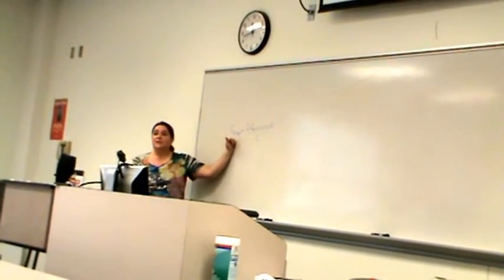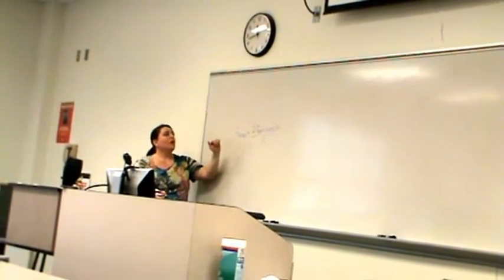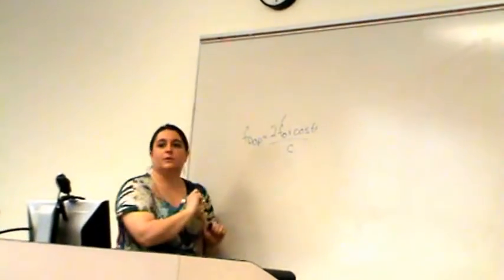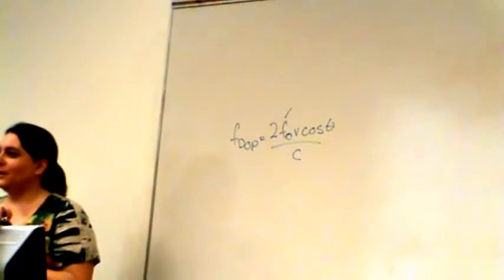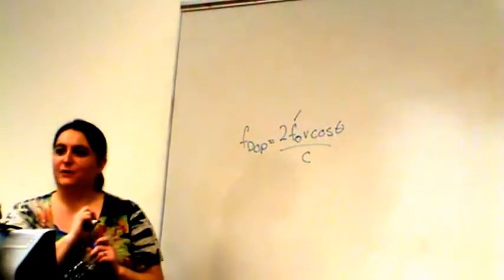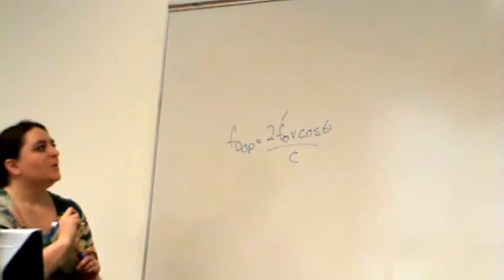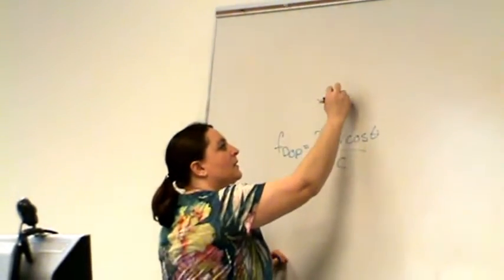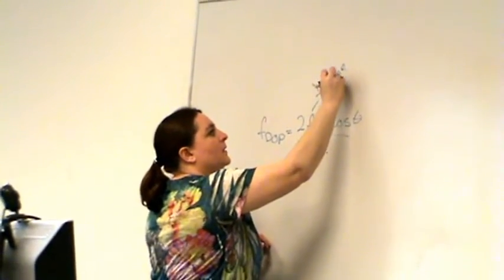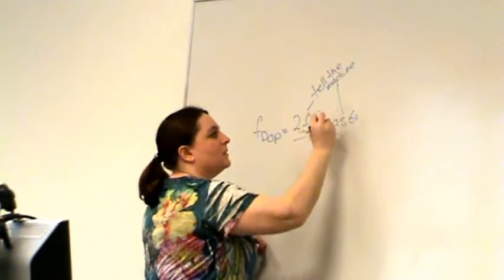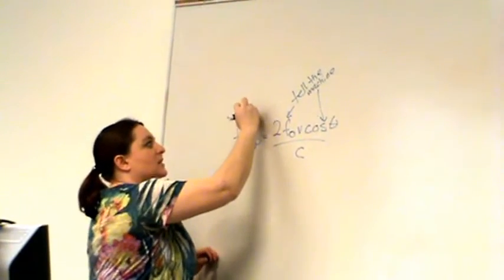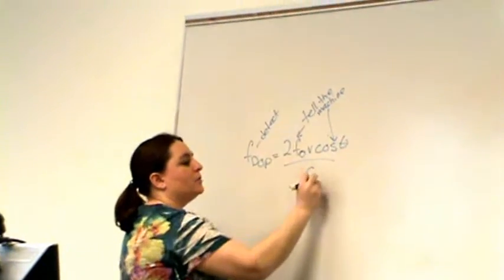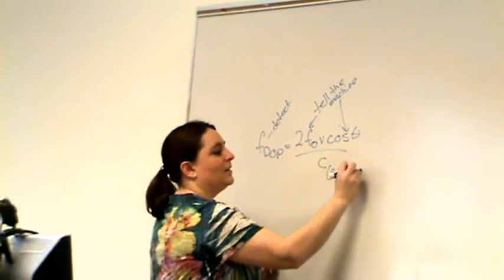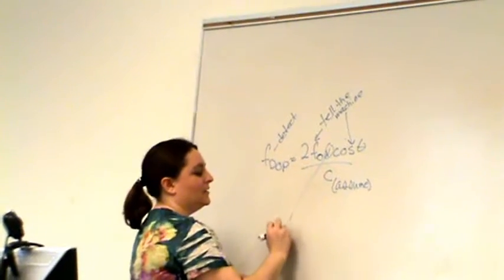Anyway, so remember with Doppler, you're detecting the Doppler shifted frequency. You know the operating frequency. This is the one that you picked up the transducer and you told the machine. Now you know that it's not really the frequency of the transducer, but whatever that transducer decides to do Doppler at. But you tell the machine this, and you tell the machine this. It detects this. It assumes this, and it calculates this.